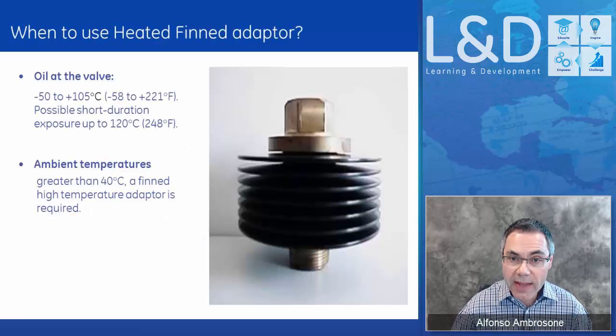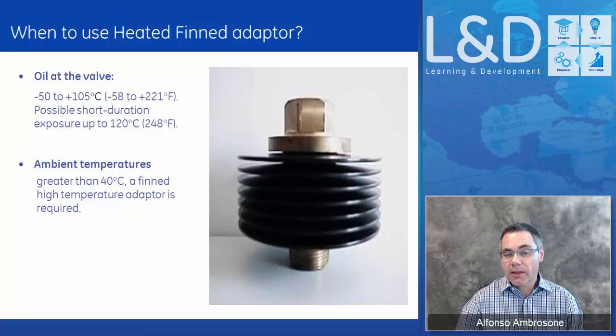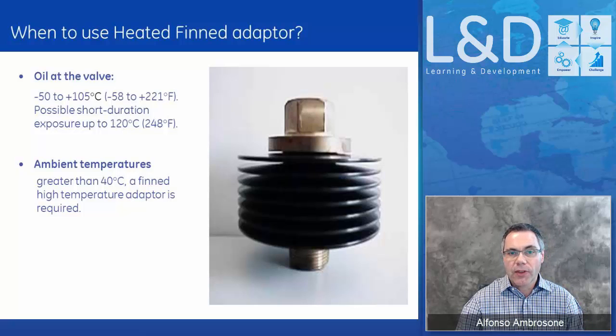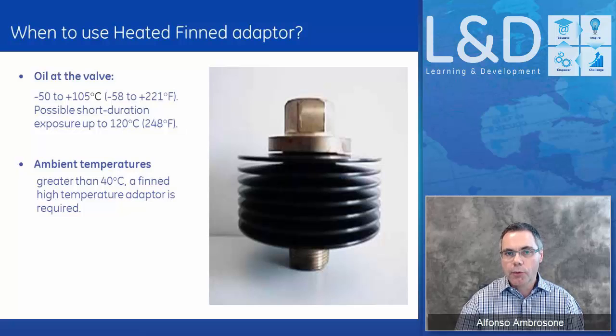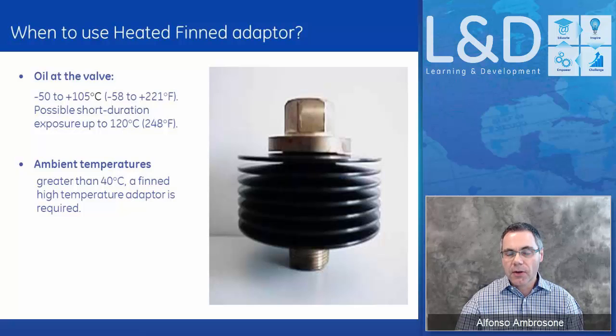Regarding the heat fin adapter for the M2: we highly recommend it in very warm countries or in applications where oil temperature exceeds 40 degrees and runs in the 50s and 60s. This will only help prolong the life of our sensor. Oil temperature directly affects the life of the Hydran sensor.